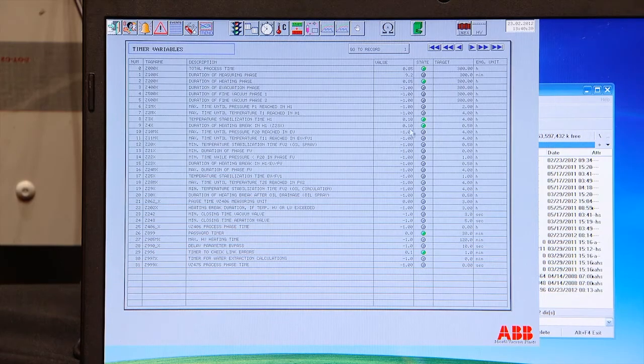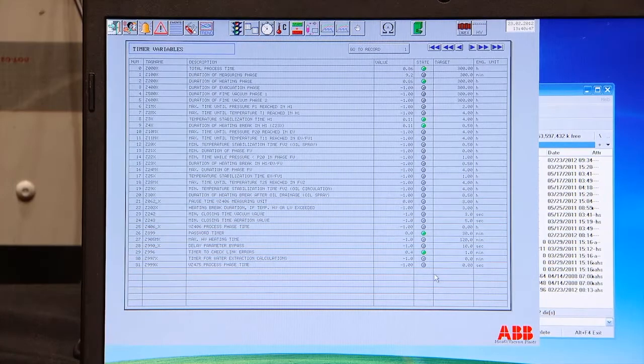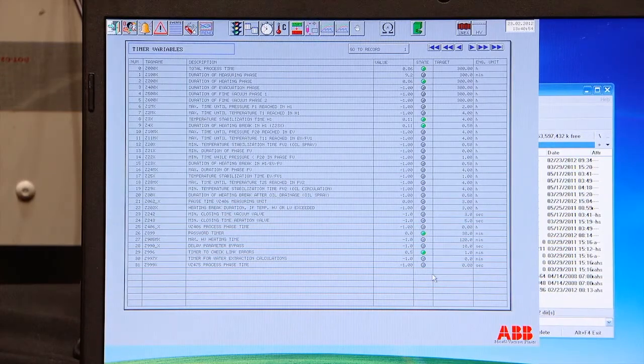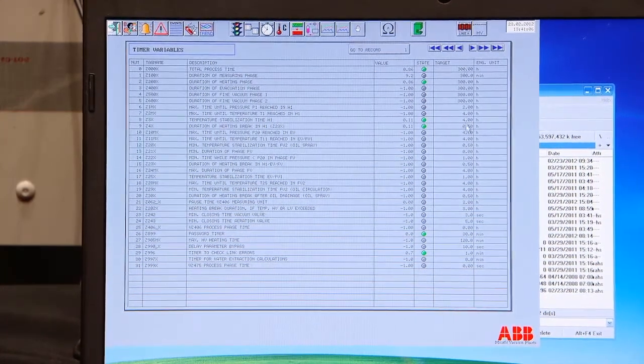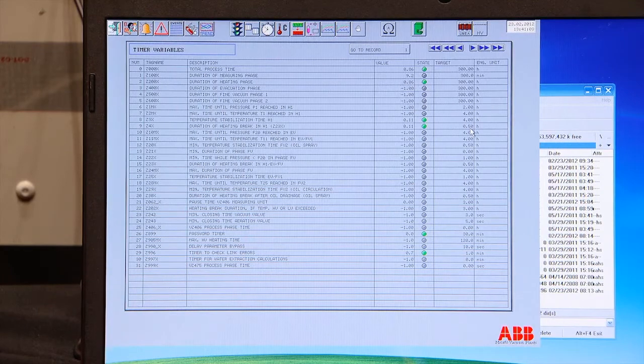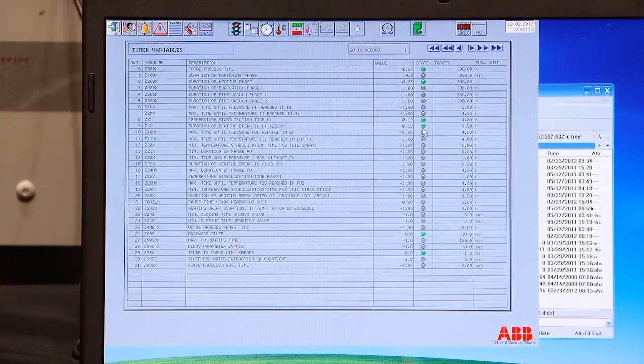So we are now at 0.10, which means 6 minutes. What we normally do now, we said we want to do the suction capacity measurement. We want to know that we are back here before the converter starts again. So we set this braking time long enough for us to be able to come back. It is now half an hour. We don't know how long it takes, so put this value now to 4 hours. When you come back, you reduce it again, so it starts when you're back.